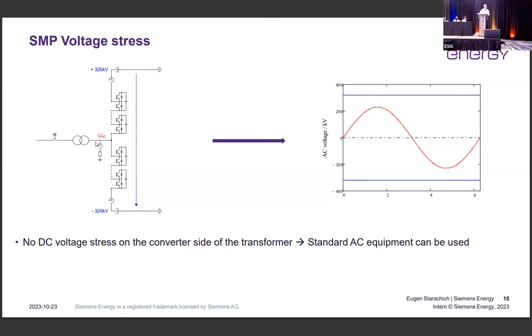All the LCC configurations that we see have a DC voltage offset, and I will explain in a minute why. That means specific equipment is required, which is why sometimes we talk about HVDC transformers. That is not the case when you use a symmetrical monopole configuration. You can use standard AC interface transformers, which makes a big difference. Also, looking at the supply chain, an HVDC transformer is more difficult to manufacture, as you need more insulation and so on. But this is not the case for the symmetrical monopole.